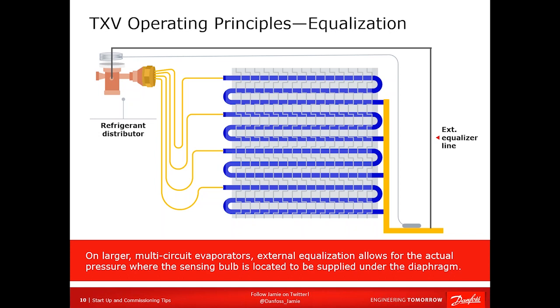Why? Because a refrigerant distributor, by its nature, introduces a high pressure drop between the TXV and the evaporator, anywhere from 5 to 30 psi, maybe even higher. So the thing to remember is, whatever temperature equivalent that pressure drop is, let's say it's a 10-degree equivalent, you will add that to the static superheat or the opening superheat of the TXV. So if there's a 10-degree equivalent pressure drop between the outlet of the TXV and the sensing bulb, you add that 10 degrees to the static superheat. So 10 plus 7 is 17 degrees, which means the TXV wouldn't even open till you had 17 degrees of superheat. So you will always underfeed an evaporator if you do not use an external equalized TXV with a distributor. And it will act just like the TXV is too small.